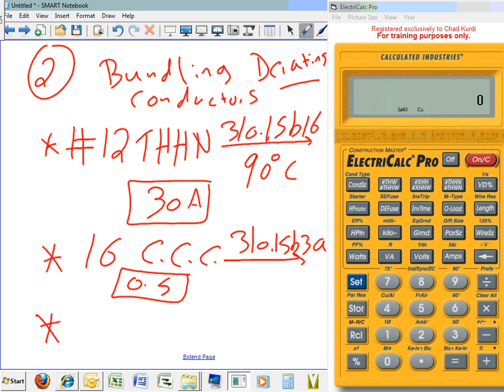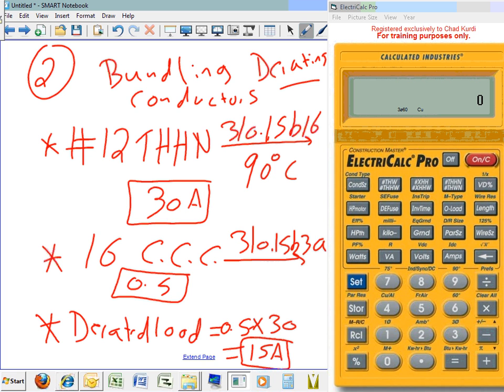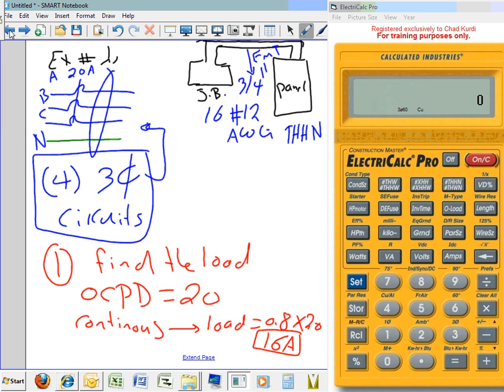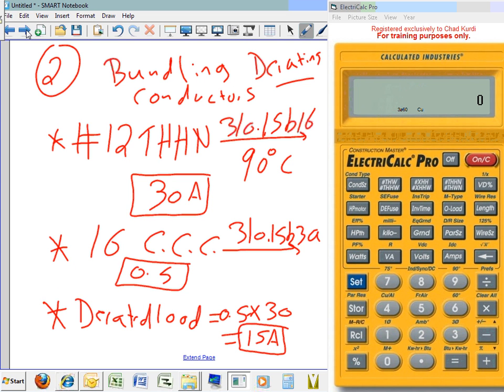The last thing to do is the derated load out of this conductor, which is 0.5 multiplied by 30. And if I still have my brain, that will give me how much? 15 amps. How many amps have I lost because of bundling? Only 1 amp. Remember, this is the scenario: you can't go more than 16 under any circumstances because it's a continuous load. So if I end up with 17, can I use 17 out of it? No, 16 is the max. Because of derating, I end up with 15. So which one am I going to stick with? The lowest, 15. So 15 amps.